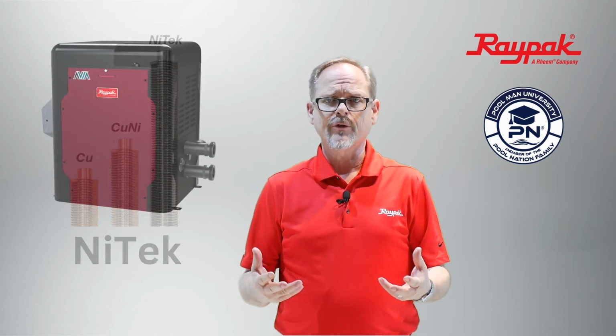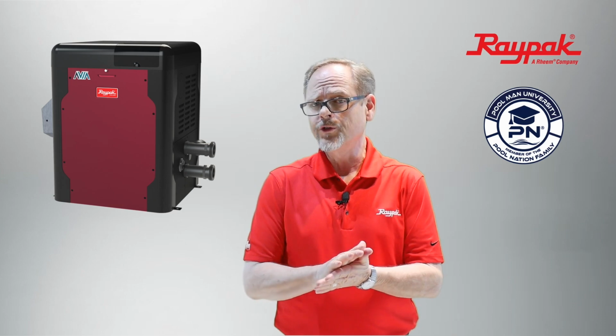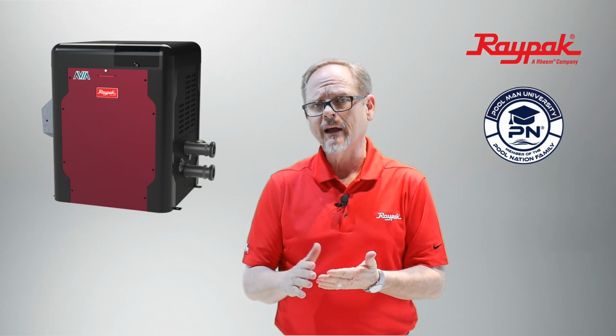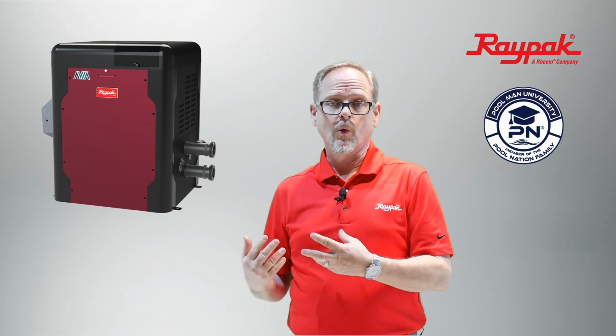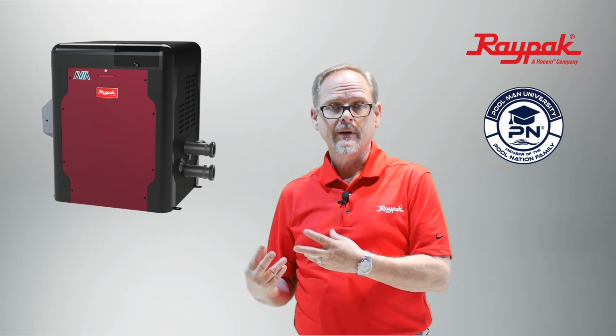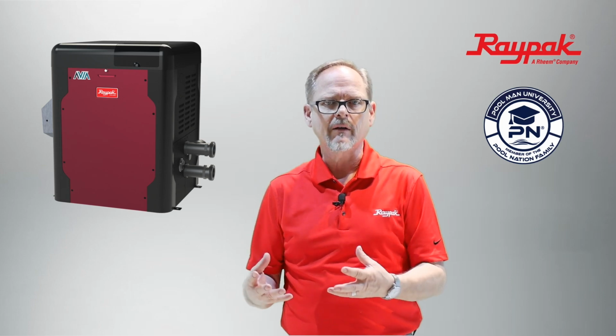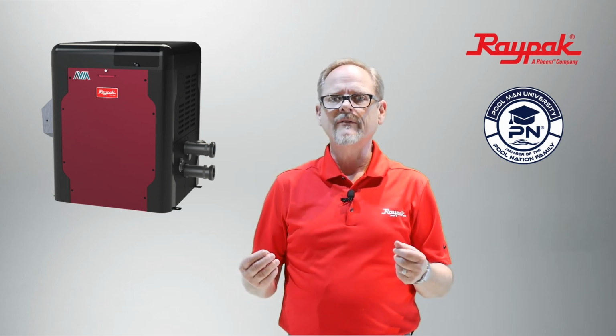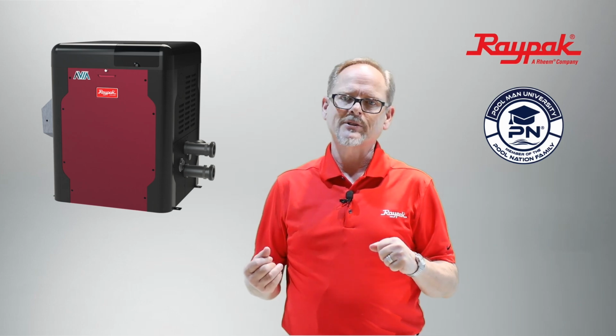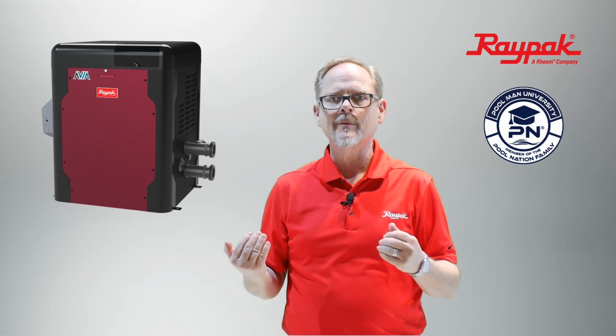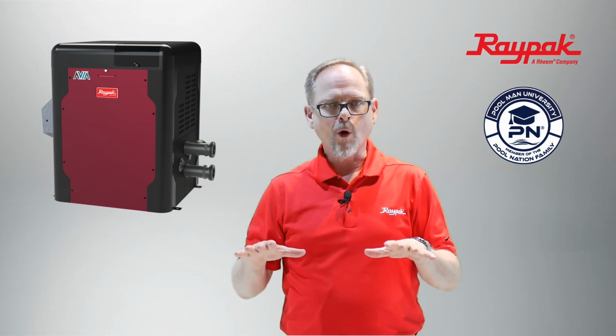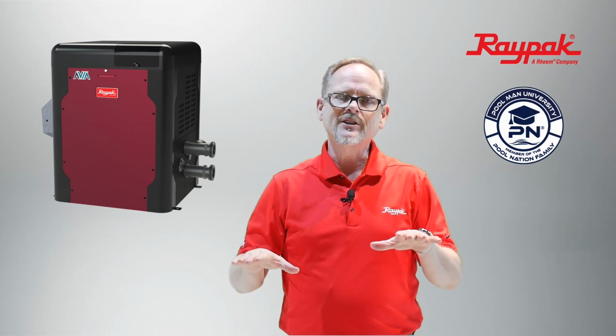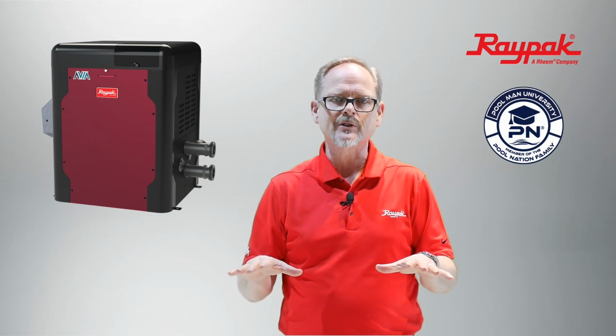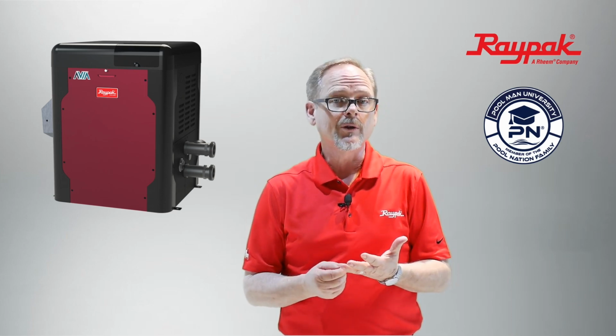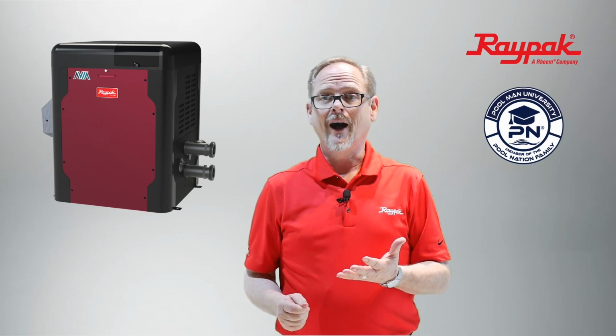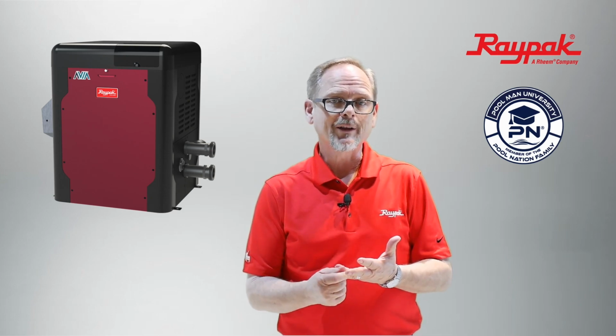This heater further differentiates itself given that it has dual temperature sensors. Other heaters on the market have one incoming sensor. This tells you the temperature of the water coming in and lets the heater know whether or not it should fire. Okay, well, we still have that, but we've added an exit temp sensor. So we're measuring the temperature of the water coming and going, and the board in the heater is measuring the difference between those two temperatures to determine things like whether or not the flow through the heat exchanger is correct, whether it's moving too quickly or too slowly.